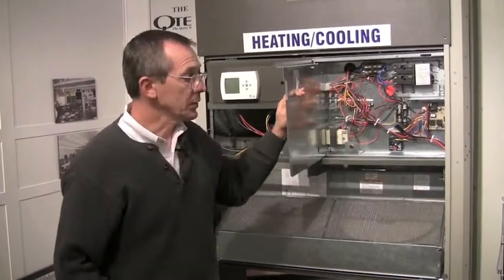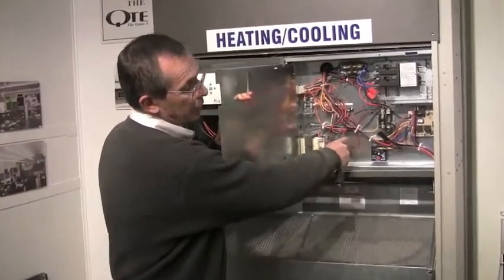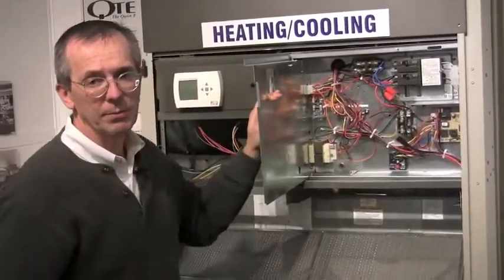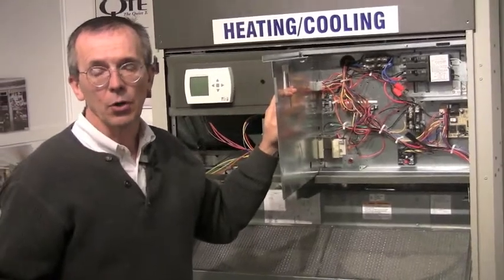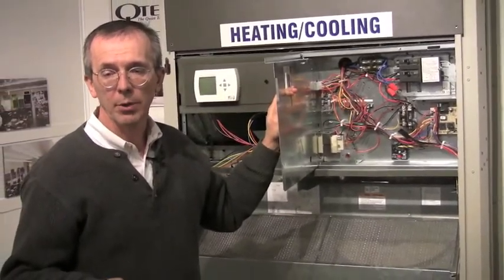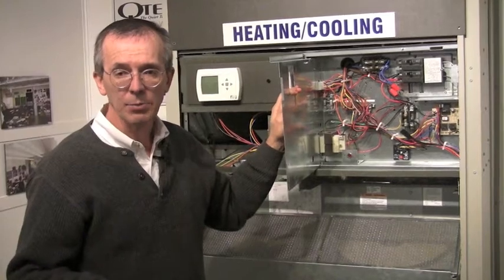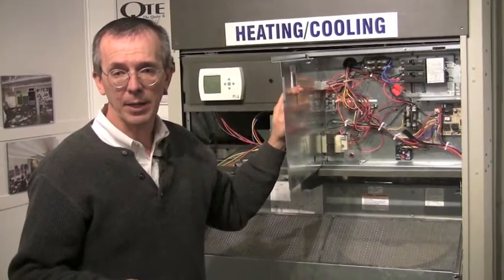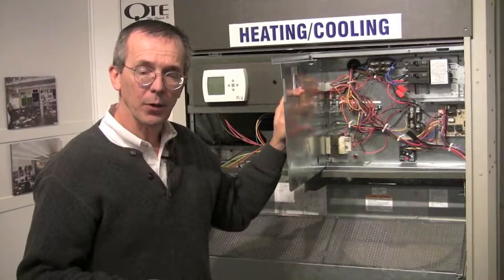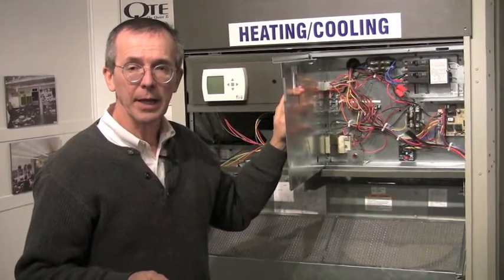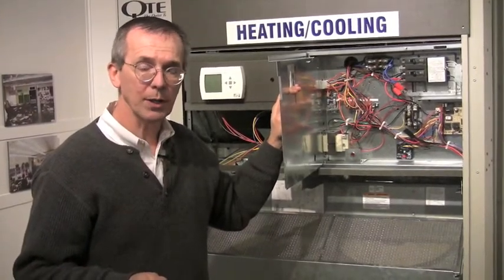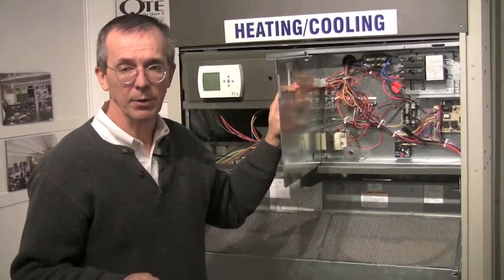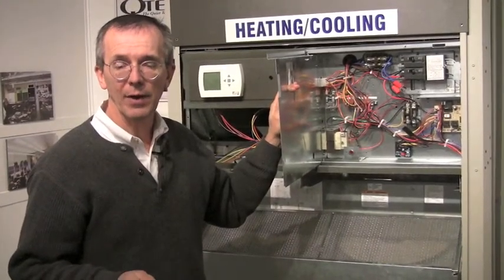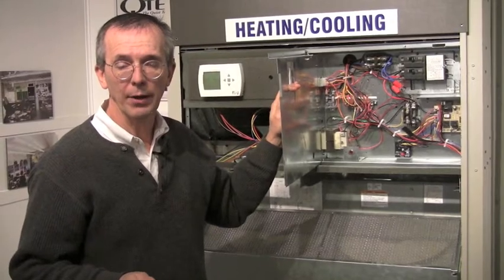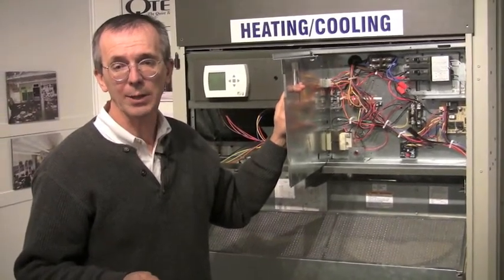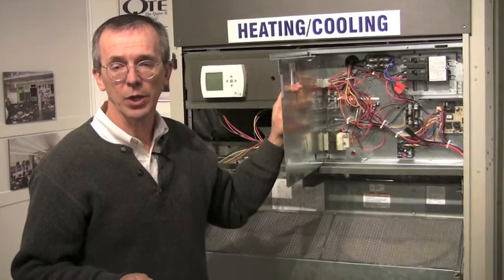And on all 3-phase units, a phase monitor is installed in this position. If you know anything about scrolls, if the legs are wrong, the compressor will run backwards. The phase monitor will keep that from happening. A red light will appear on the monitor indicating that the phases are wrong. Either switch them at the unit or switch them at the breaker panel. It's also there if you have a high voltage problem or you have a brownout or you lose a leg of power coming into the building. The phase monitor will shut the compressor down.